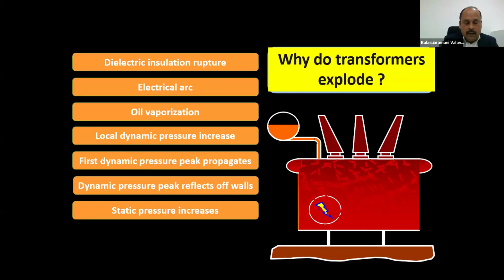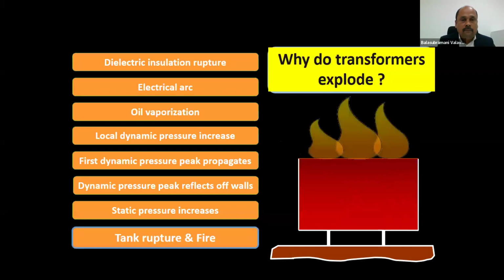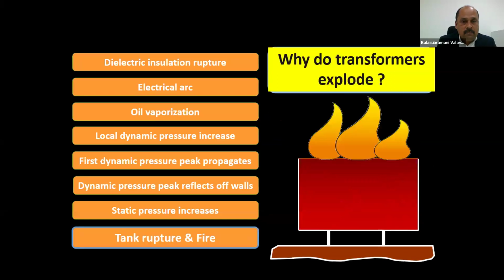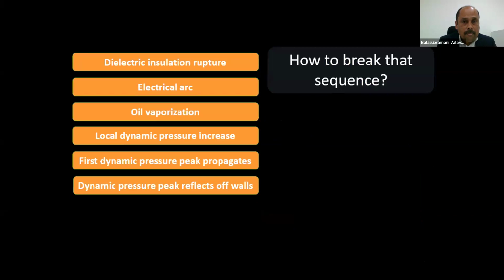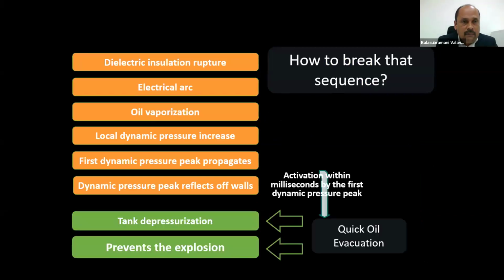So in general principle, if you look at whatever thickness is maintained, if you don't have the surge system, it should be at least 8 times. Suppose you have a wall thickness of 10 mm. If you don't have a surge system, you have to keep at least 8 times that thickness. Same way, if you have the surge system, how does it work? Everything happens starting from dielectric insulation, electrical arc, oil evaporation, dynamic pressure increases, and the dynamic pressure propagates and then leads to static pressure.